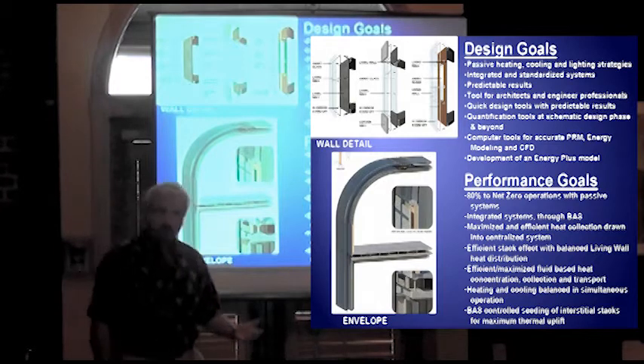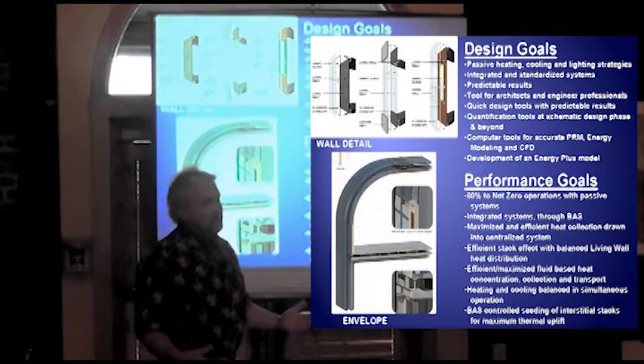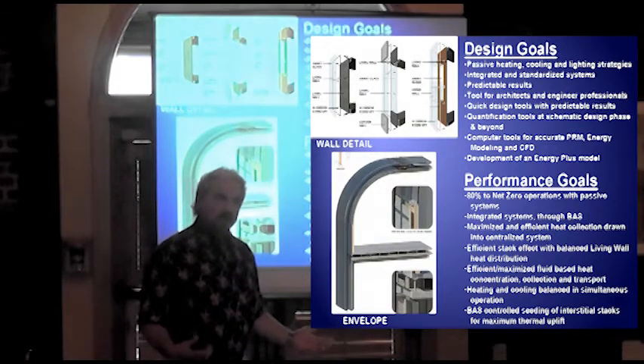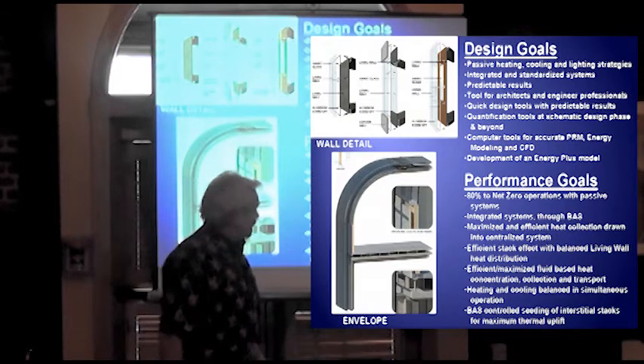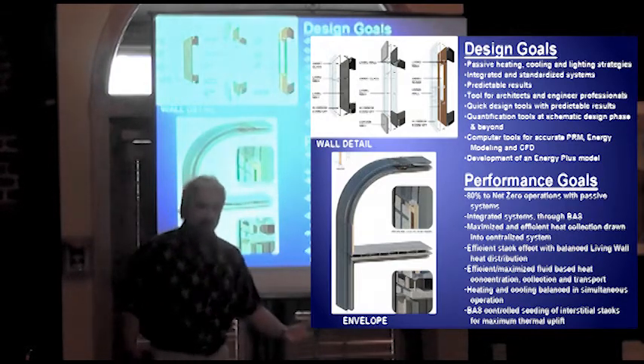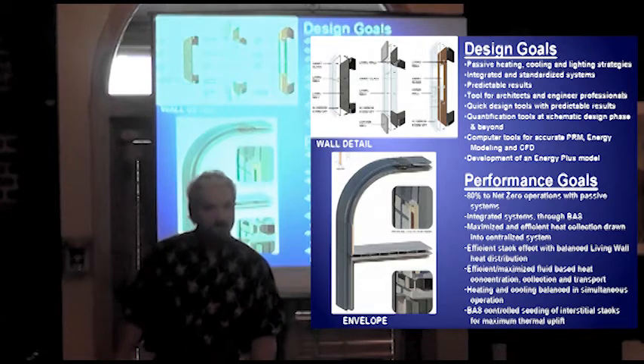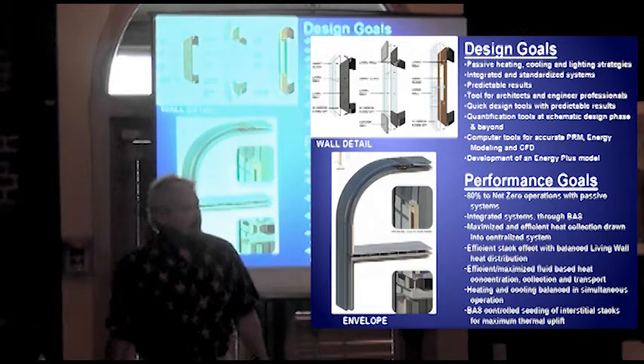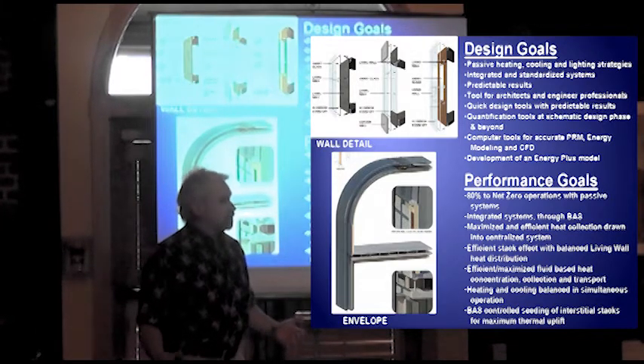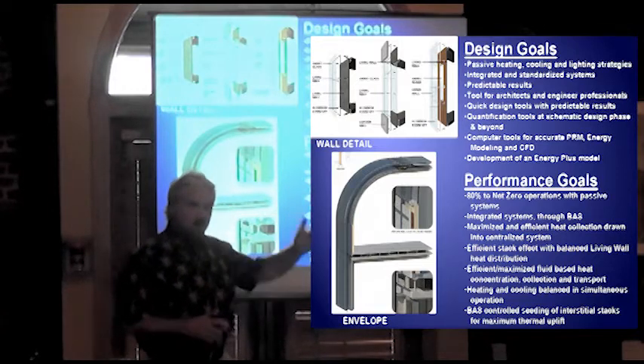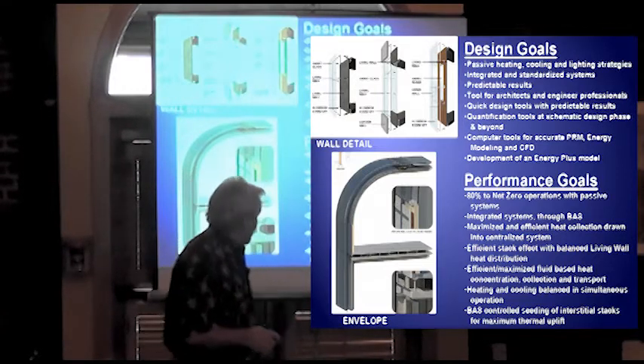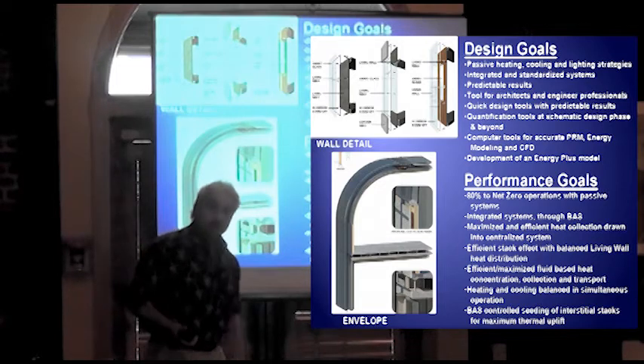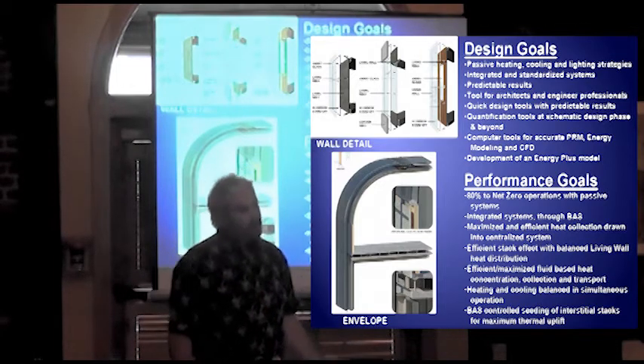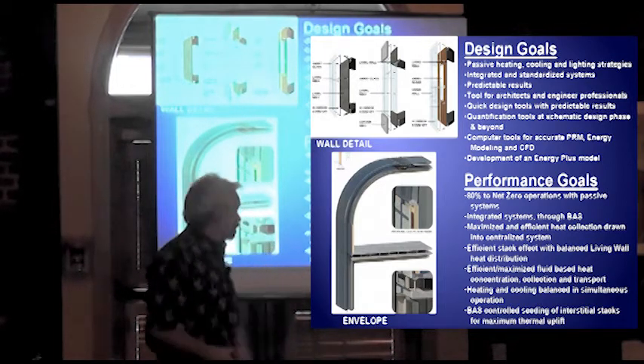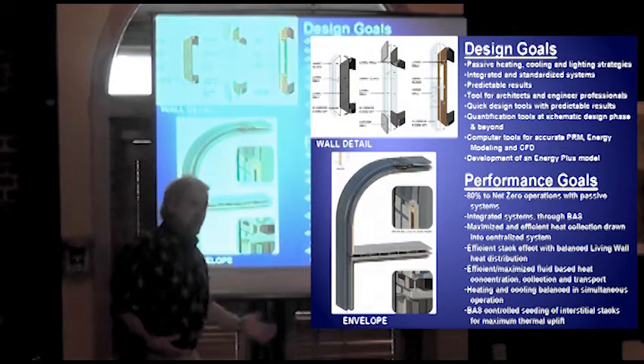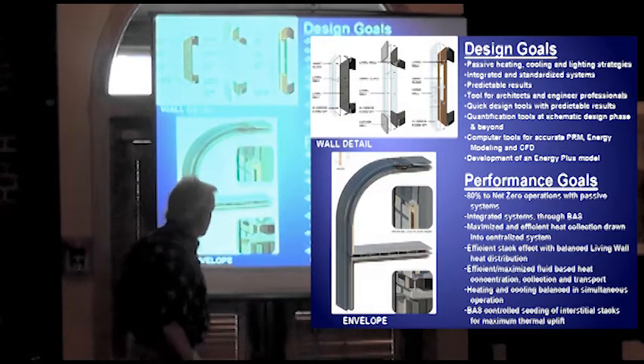So cooling is the problem. The thing I like to say is the hotter the better for passive cooling. If you're coupled to a ground or some sort of thermal sink, the hotter it is the greater the temperature differential within this thermal interstitial wall, and the greater differential creates a faster uplift of air and a greater volume of air. So the hotter the better moves more air on the hottest days.